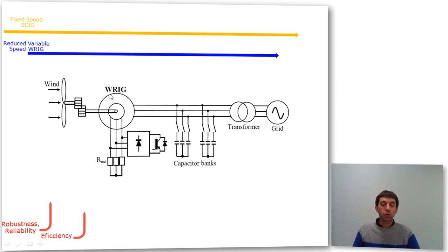Therefore, we can say that a second family of wind turbines started to appear, based on the wound rotor induction generator. It still uses a very strong design of machine, but we are starting to put here very simple power electronics, diodes and IGBT combinations, in order to achieve a variable resistance and obtain at the wind turbine a rotational speed variation, higher than the one obtained before. With this we obtain better efficiency.